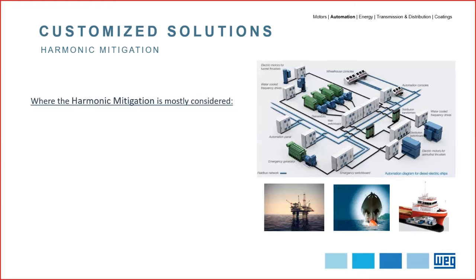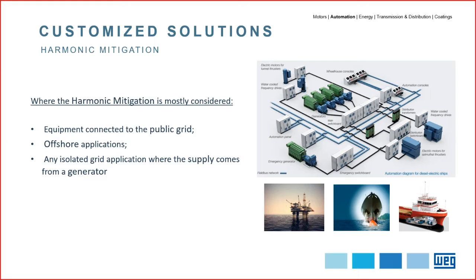And which are the most critical scenarios where harmonic mitigation is considered? When we have equipment connected to the public grid, in offshore applications, and in any isolated grid application where the supply comes from a generator. It's important to say that these are only examples, and harmonic mitigation may also be required for different applications, always depending on customers' requirements.